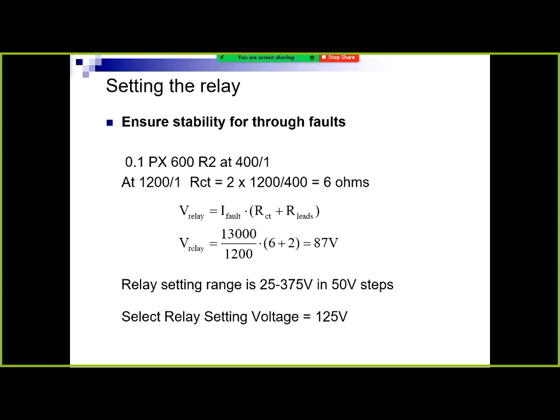So this is one of those high impedance or old electromechanical style relays. So they have the plugs and dials and things like that in them. So the settings range from 25 to 375 in steps of 50. So you haven't got a continuous range. So your options are 25, 75, 125. That's it. So we know it needs to be at least 87. It can't be less than 87. The next available setting is 125. You set the relay. That's it.